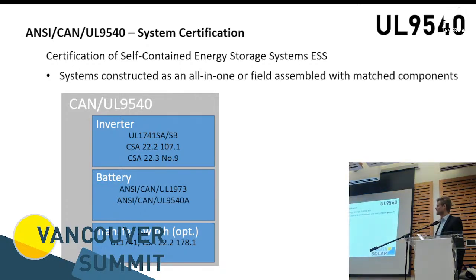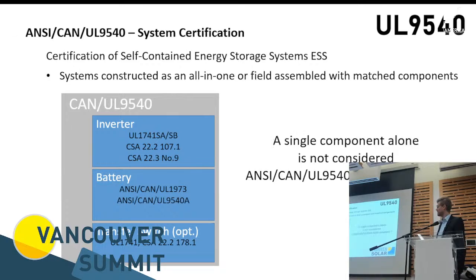So for the inverter, for example, it's the UL 1741, which a lot of people already know. It's a hot topic also with the SB certification that is required specifically in Alberta and the Western Canadian market. The battery typically has their own certification for the battery cells and the battery module and its fire propagation testing. And if you wrap that system up with a transfer switch, can be a partial home or full home backup, that transfer switch has also certification. But together, that system will be a UL 9540 certified system.